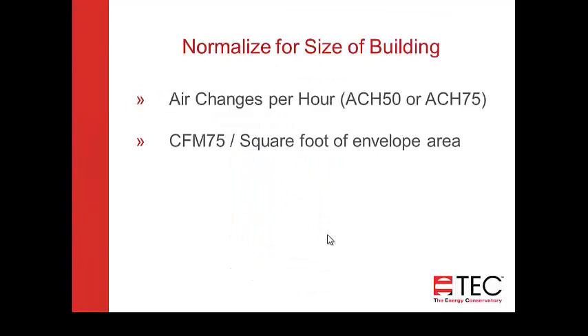Normalizing for the size of the building is typically done using the volume or the square footage of the surface area — the envelope area. More and more standards are moving towards CFM per square foot of envelope area, for obvious reasons: the building leaks at its surface area, not its volume. There's not a good correlation, especially in bigger odd-shaped buildings, between air changes per hour and CFM per square foot of surface area. Because the leakage is on the envelope area, it's best to use that metric.